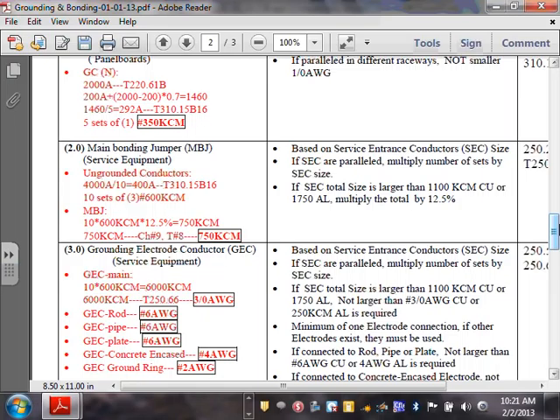Any comments, guys? Any questions about that? And here's another. You brought up a very good point. If that becomes a big conductor to work with, that's where bonding one conduit at a time is an alternative for this method. By the way, if you don't want to work with 750, what's your option? This is option 1, daisy chaining. What's option 2? You know what option 2 is?